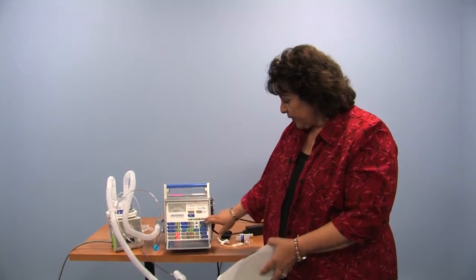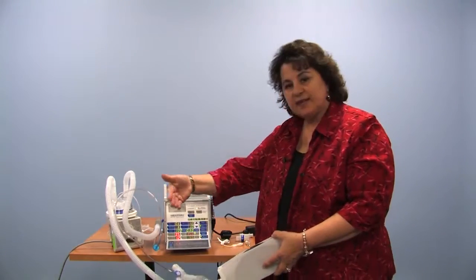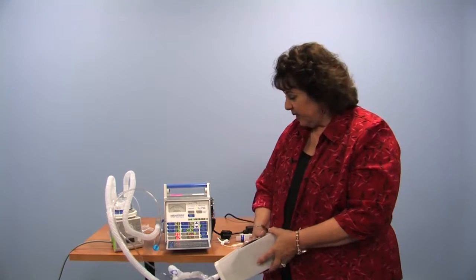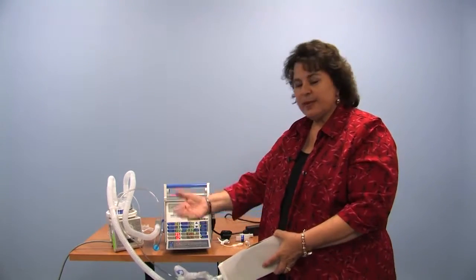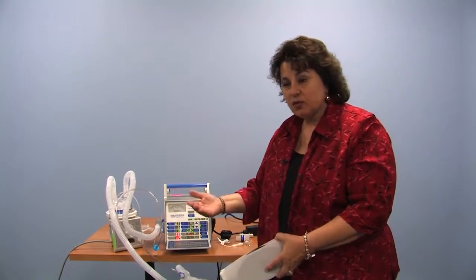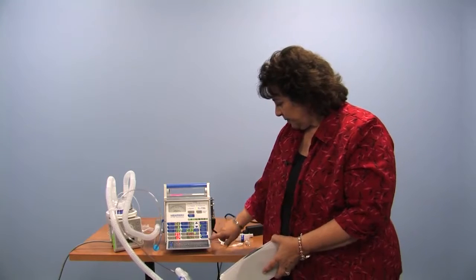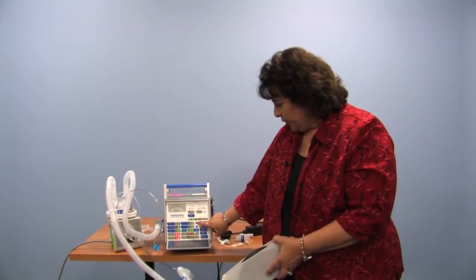These are measured parameters. They're measured here. They come out of the machine. It's what the machine is sending out. Some machines measure what comes out of the patient. Some machines measure what goes into the patient. So these are all what we call inhaled numbers. We talked a little bit about minute ventilation. So the machine is looking at how many breaths and the size of them.